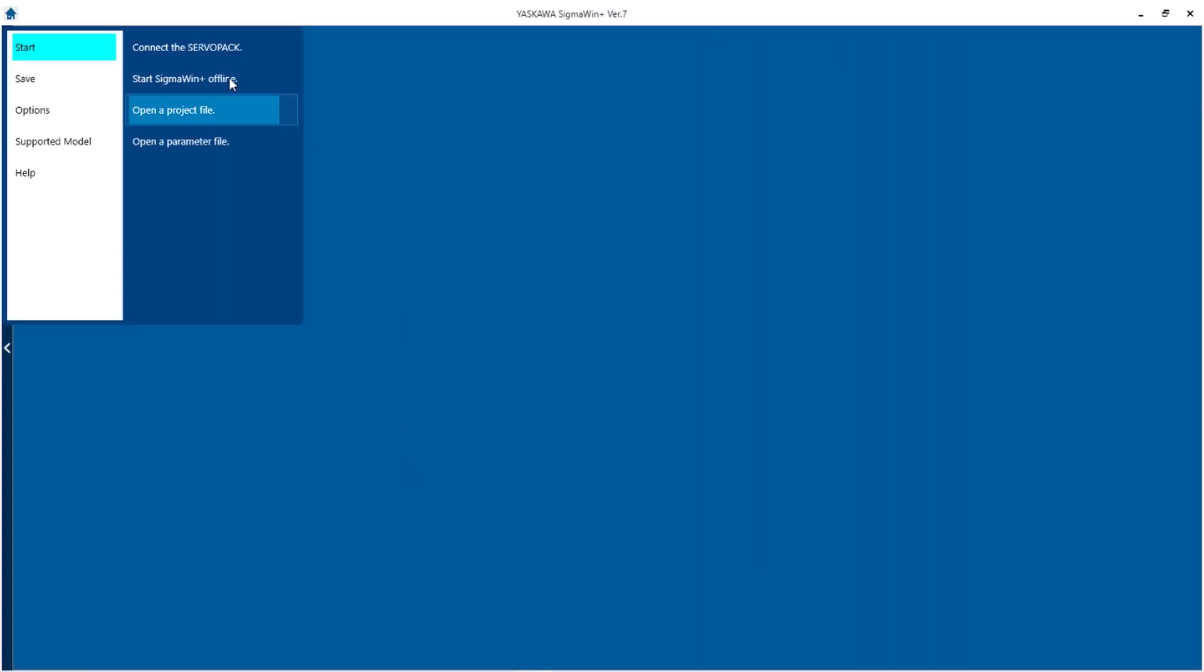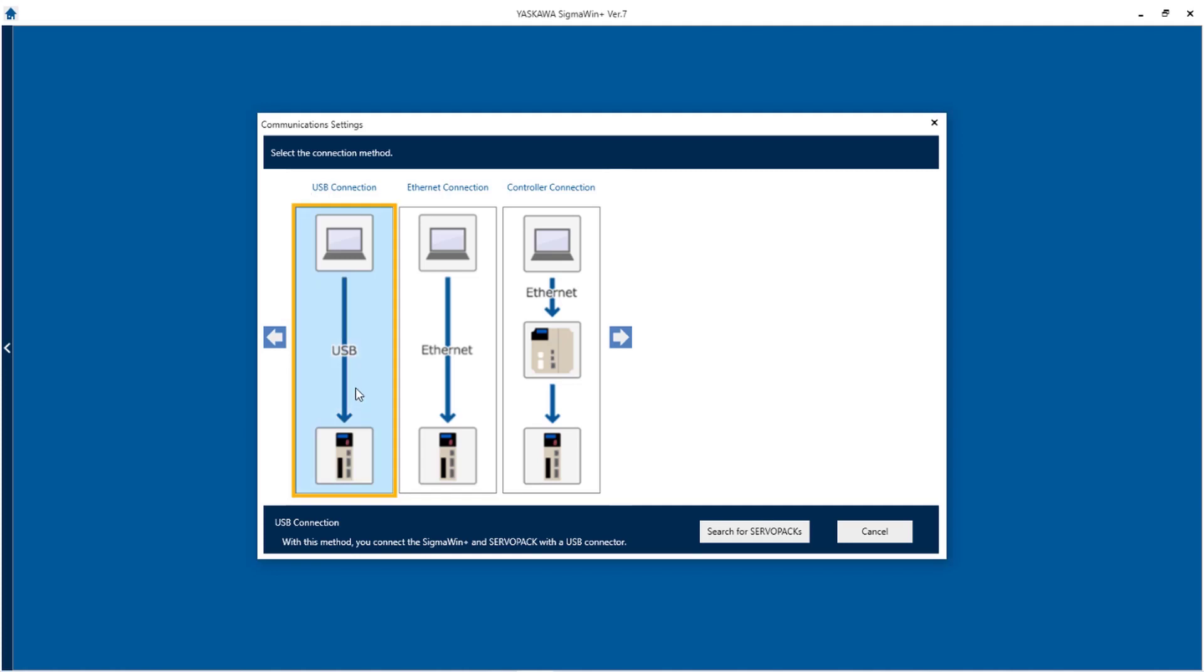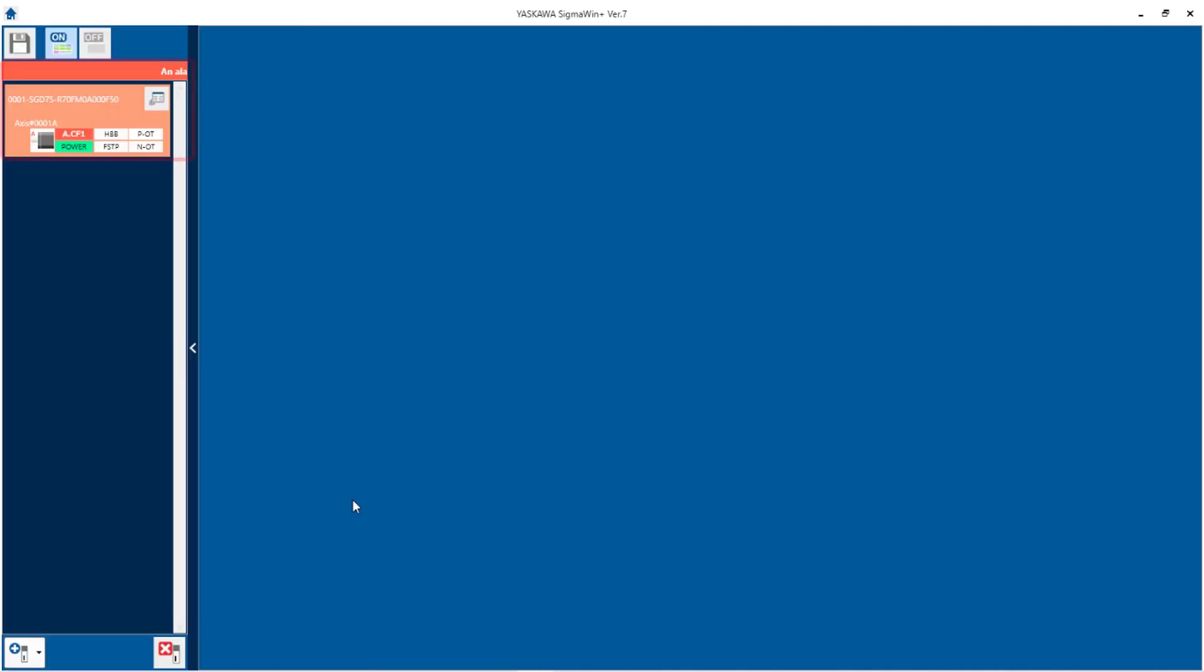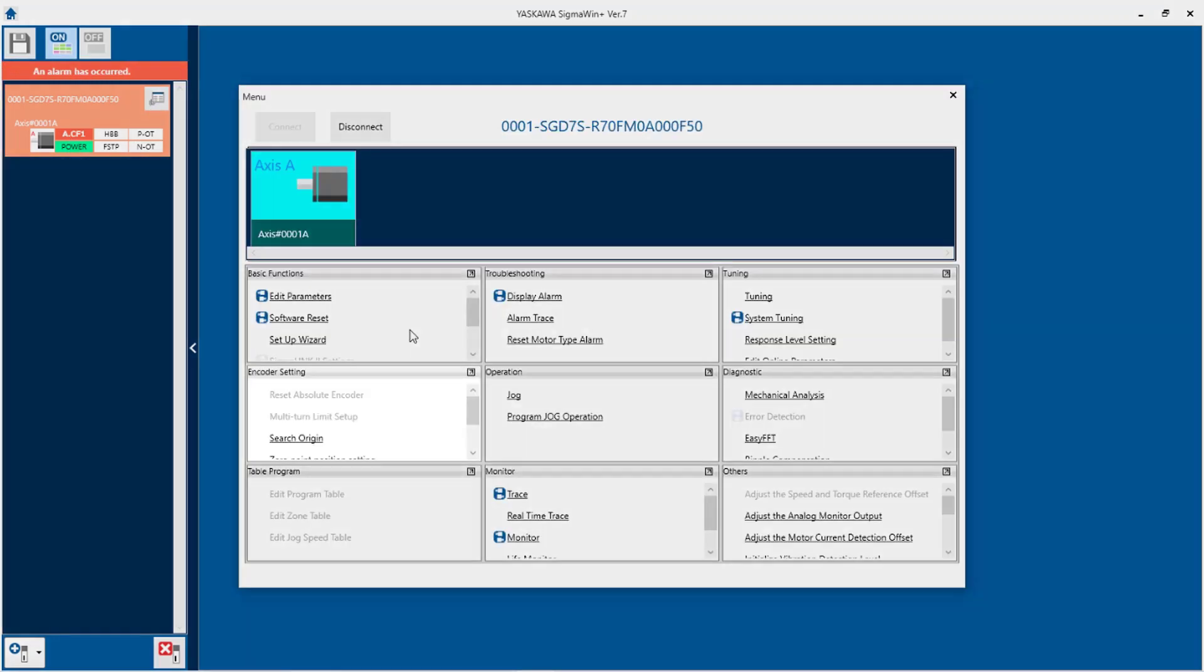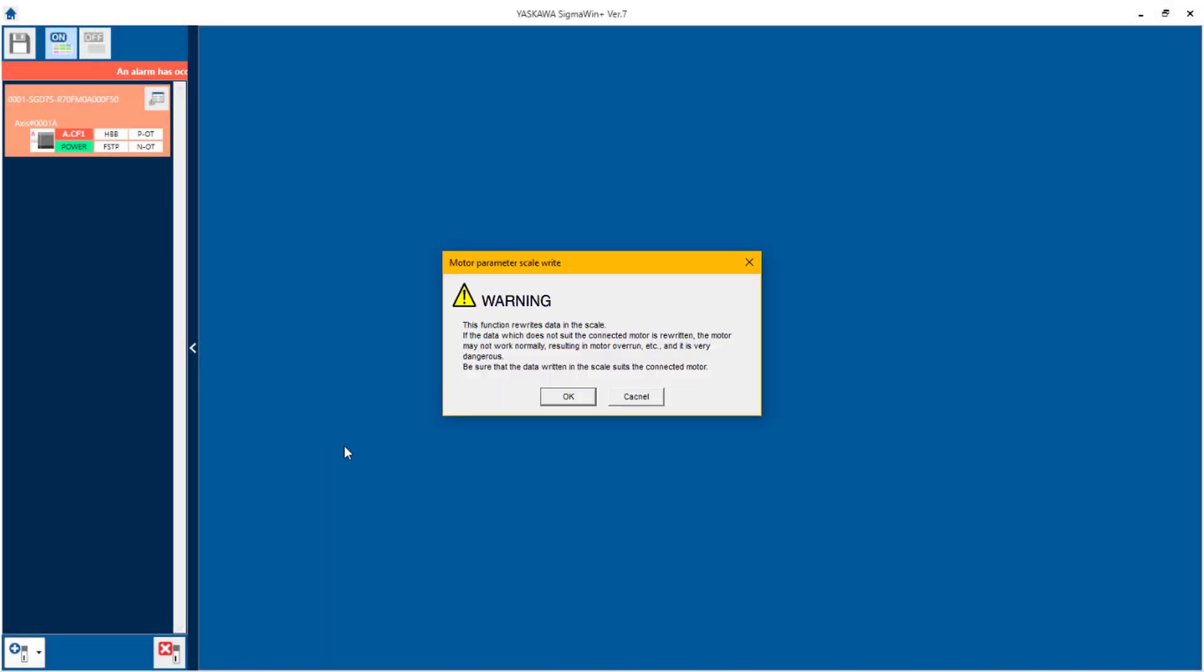I'm going to open SigmaWin+ and connect to the servo pack. I'm going to use the USB connection. When connected I can still see that it has an A.CF1 alarm. So I need to go to the main menu. And under the encoder settings section, I'm going to go to motor parameter scale write.